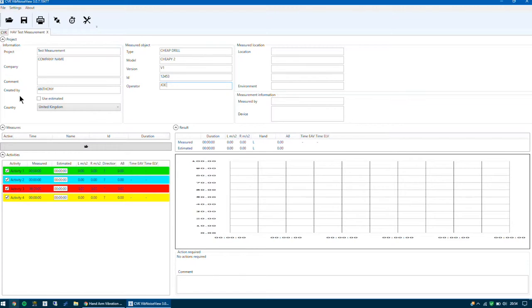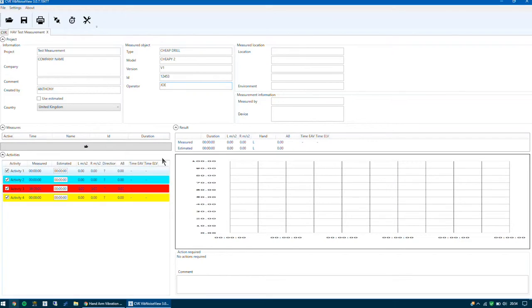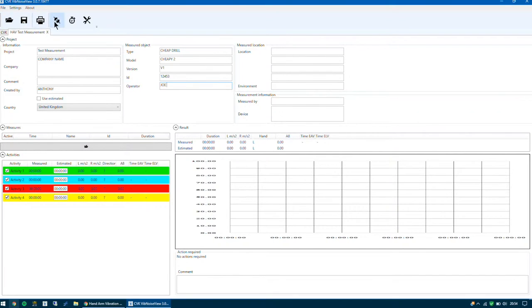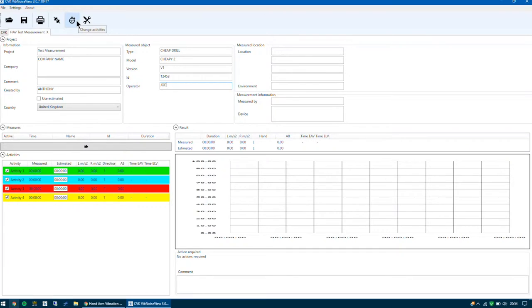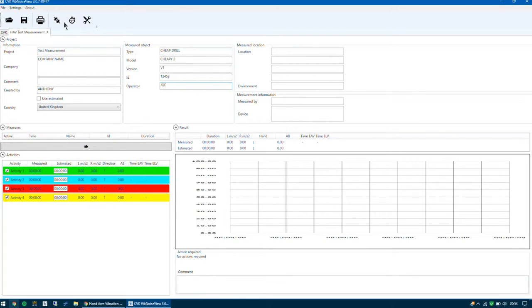In the middle of the screen we have the measures, just below that we have the activities where we can specify certain activities for our measurement, and to the right we have our results. There are six icons at the top of the screen: the first is to open a saved project, the second is to save the file, the third is to print the report, next is the connect icon to connect to the Vib indicator, then we can change the activities, and finally we have the calibrate tool.